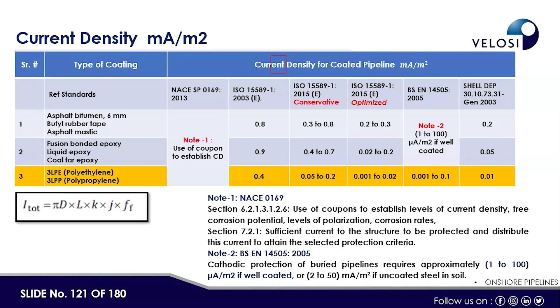Then what is the next factor? For this 10% surface area, how much current density do you need? Here the different standards give us the current density, in milliampere per square meter. So for 1 square meter, how much current is required? Go to the next slide.